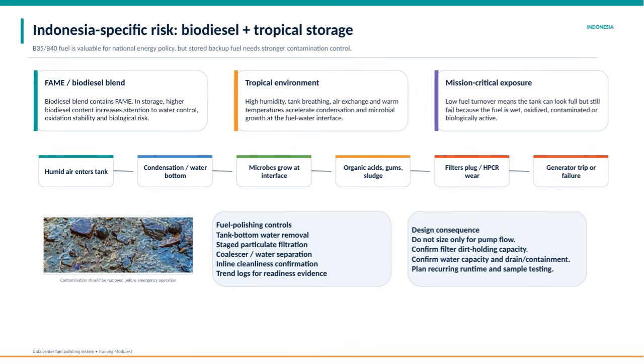Because Indonesia's tropical environment is characterized by high humidity, warm temperatures, and constant air exchange in storage tanks, condensation forms more readily. This condensation creates water at the bottom of fuel tanks, providing an ideal environment for microbes to grow at the fuel-water interface. Over time, this microbial activity can produce organic acids, gums, and sludge, which not only degrade the fuel quality, but also cause filters to clog and increase wear on high-pressure common rail systems.